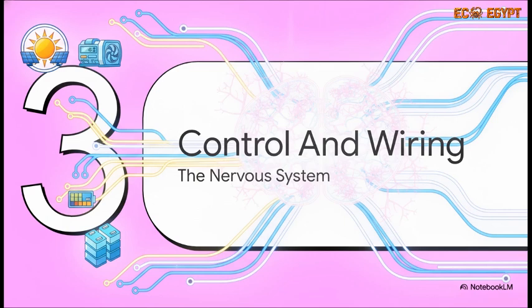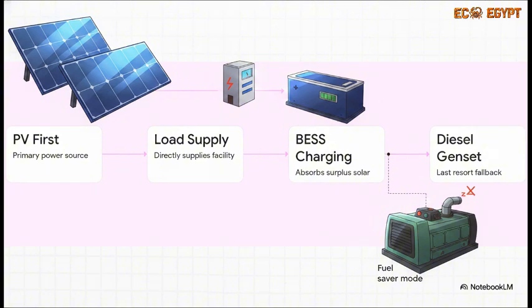This is the nervous system of our energy island. So we have the muscles sized, but they need to communicate flawlessly. The energy management system executes a really rigorous power priority sequence. Priority 1 is always solar PV feeding the load. Surplus solar, that moves to priority 3, charging the BESS units. The diesel generator is strictly priority 4. It's basically a last resort that only auto-starts when the battery hits a critical low. This specific logic maximizes your solar fraction while completely preventing that catastrophic wet stacking we just talked about.